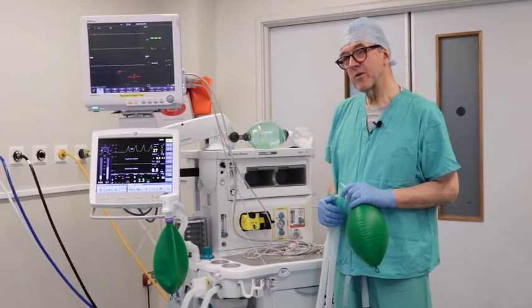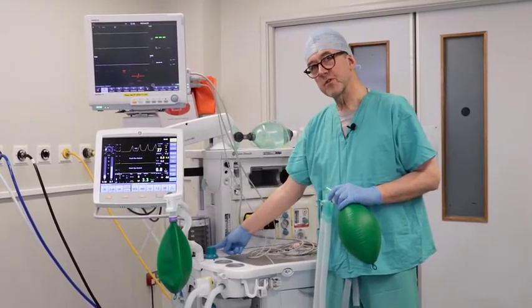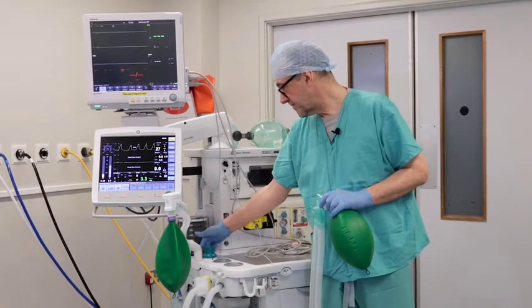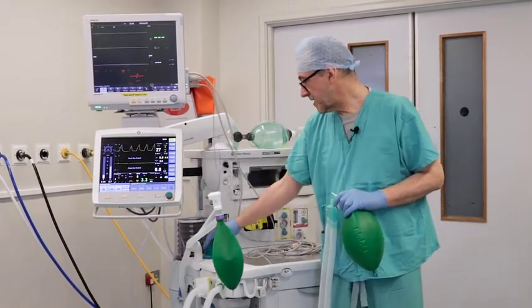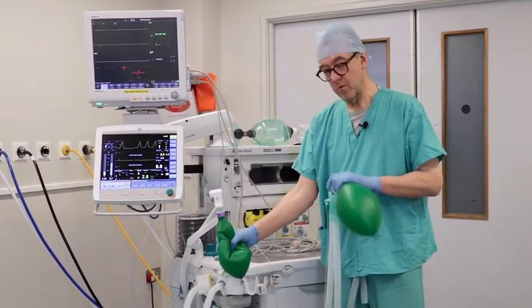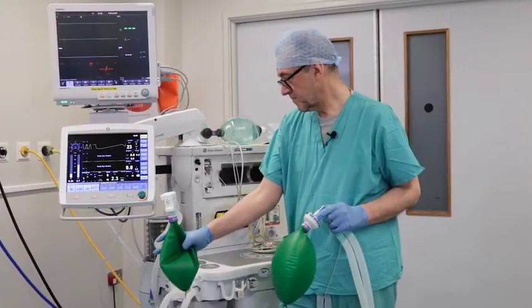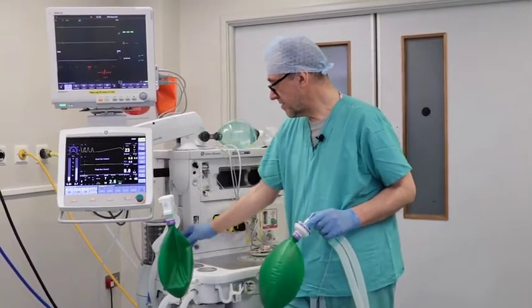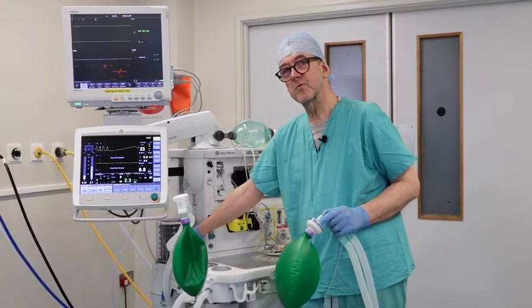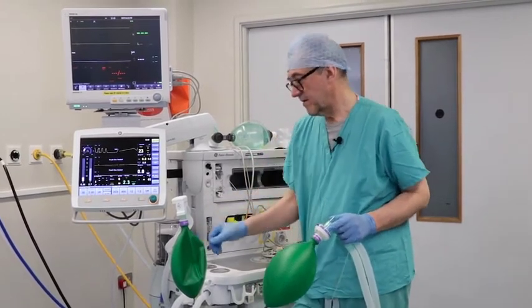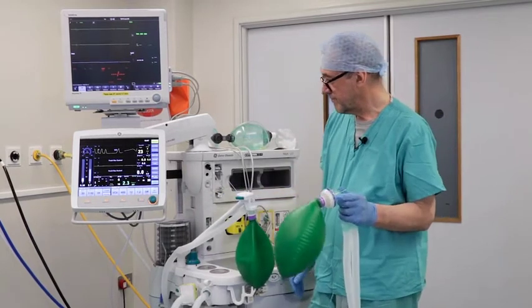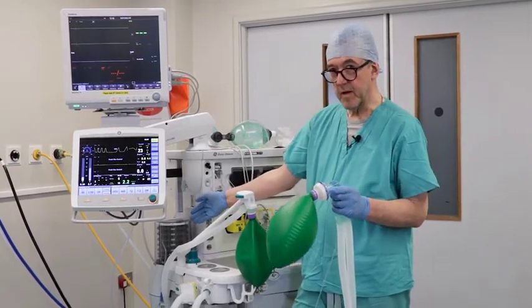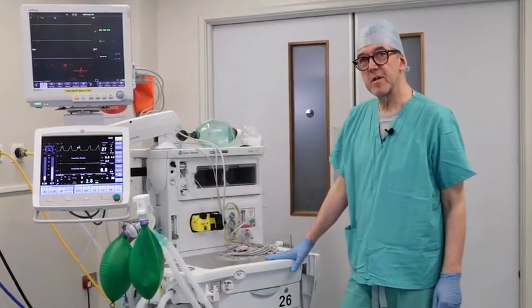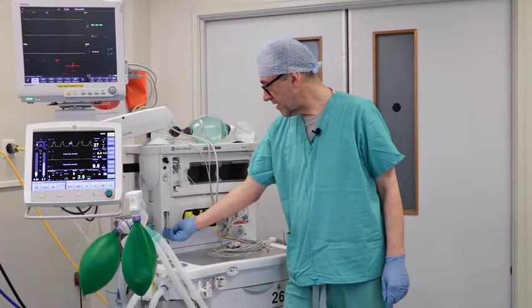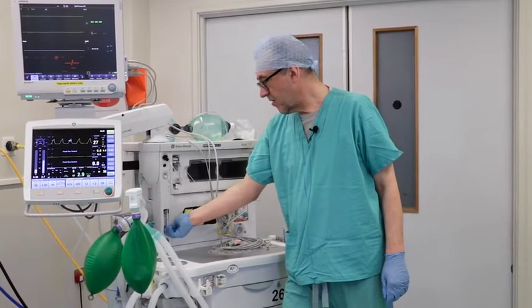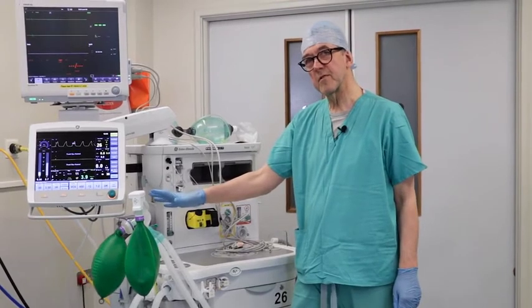The ventilator can be operated in manual mode by pushing this switch from the right over to the left. The patient is now ventilated using the bag in manual mode. Okay, to return to automatic ventilation, the switch goes from left to right. Now operated by the bellows again. So auxiliary parts of the machine include a port here and a flow meter for delivering oxygen, which is completely independent of the ventilator.